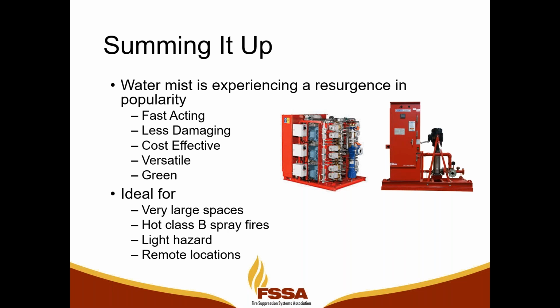They're cost effective especially on very large spaces where it might not be practical to use a gaseous agent, because we're paying for every pound of gas that we use. So there are tipping points where you would say water mist is my best option because of this volume. They're versatile. You can use a single pump style with the right water mist nozzle and protect hundreds of different environments by using different nozzles and different design parameters. And water itself applies to so many different hazard types. And obviously water mist is green. Water mist is also ideal where we've got very hot Class B spray fires.